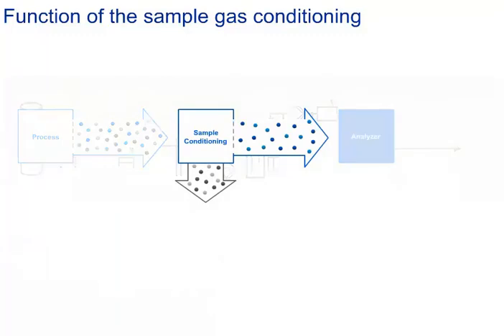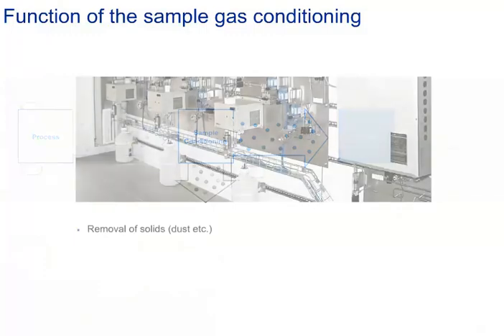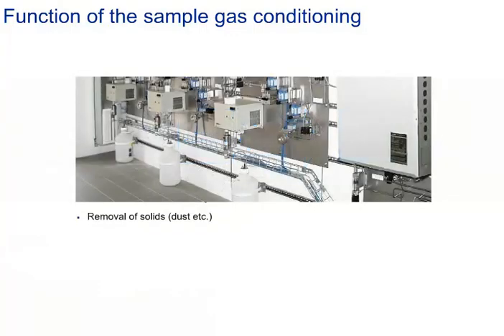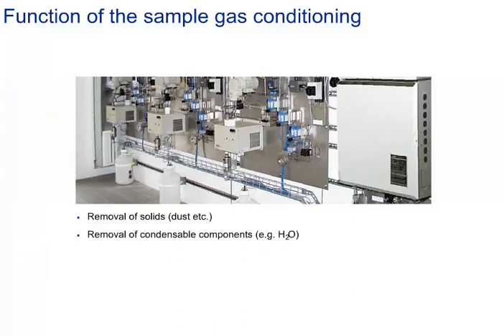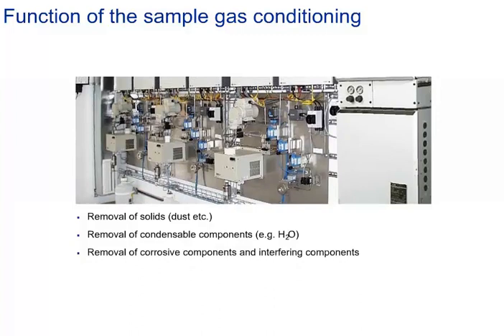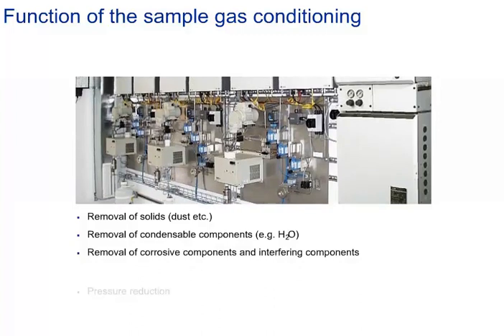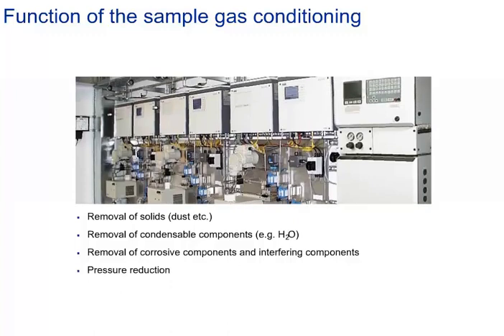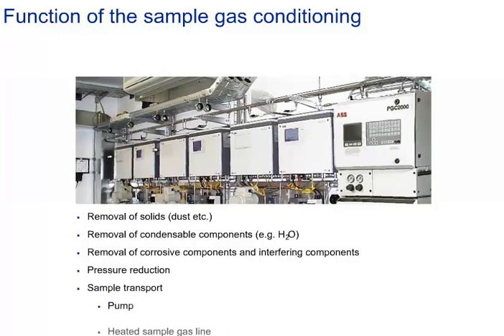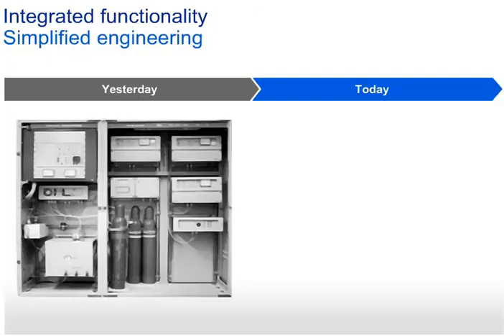The sample handling system has the ability to condition all kinds of gas mixtures for a reliable measurement. It can be tailored exactly to the needs of a specific measuring point in a process — superior and more flexible than all other methods. The main tasks include: removal of solids; removal of condensable components like water content; removal of corrosive and interfering components; pressure reduction to a range acceptable for the measuring sensors; and sample transport with special gas pumps and heated sample gas lines. These modern modules with their integrated functionalities drastically reduce the space needed for system integration.